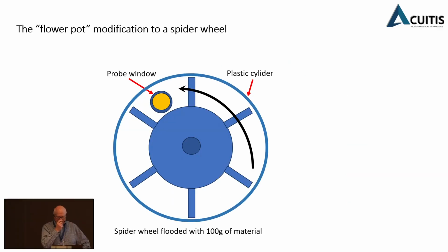One of the great things about this device, and Phil and I found this out recently, is that we wanted to look at transferring a calibration from a feed frame into this mechanical device. You go to all the lengths of figuring out how to do that transfer. But in the end, it was actually easiest just to get a flower pot, cut the top off it, and put a shell around the spider wheel, in which case it only takes probably 100 grams, and you could scan everything in the spider wheel and develop a calibration without going to all the complexities of mathematically transferring them. Just use a flower pot and collect the data in the spider wheel.